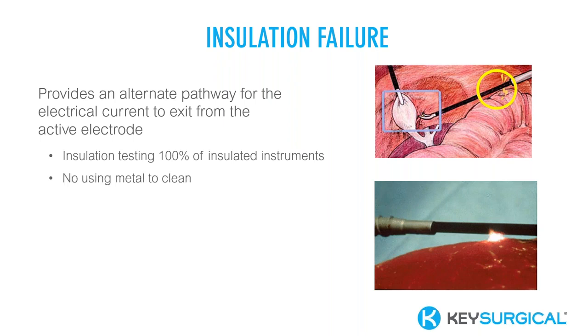Another way, we talked about this, is not to use metal to clean these instruments. Using those metal brushes or knife handles can actually damage the insulation. Handling instruments with care, using a non-slip surface in the operating room to set the instrument on, or putting them back in the holster that you have, can prevent it from falling on the floor. And of course, only using the instruments as intended. And finally, although they may not always be visible to your eye, still visually inspect these instruments. And if any damage is noted, communicate that as soon as you notice something, especially if the patient is still in the operating room, to give that time where we could evaluate it and not miss it before the patient leaves the room.